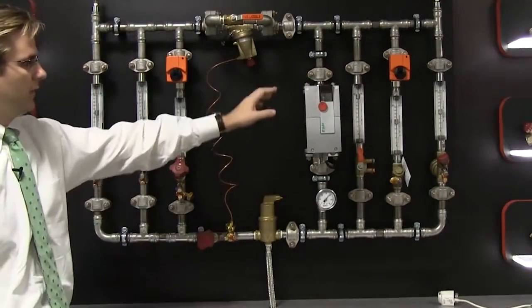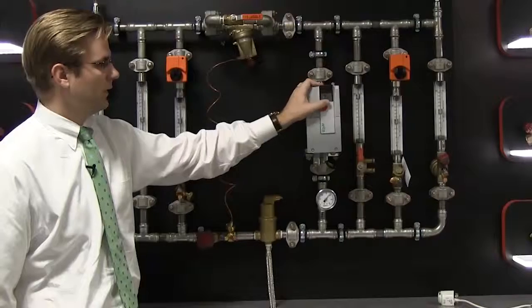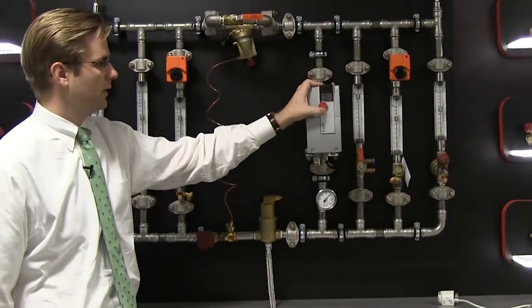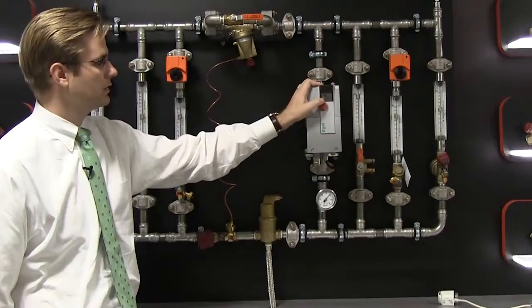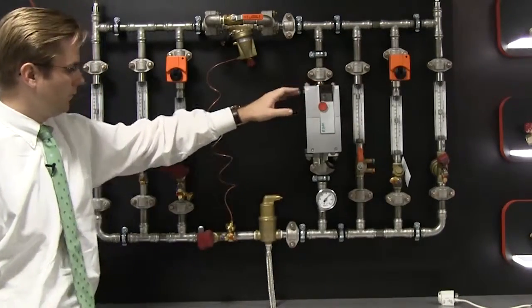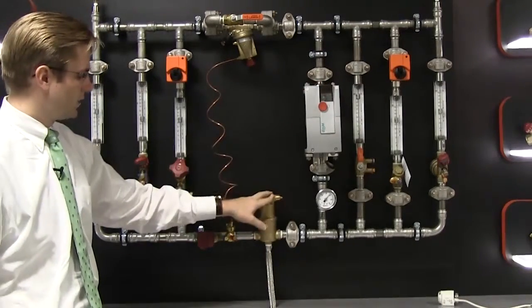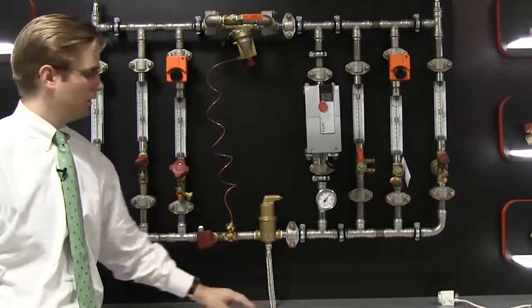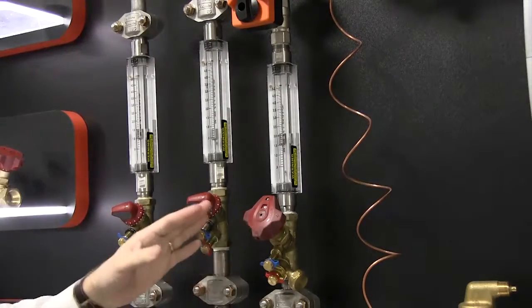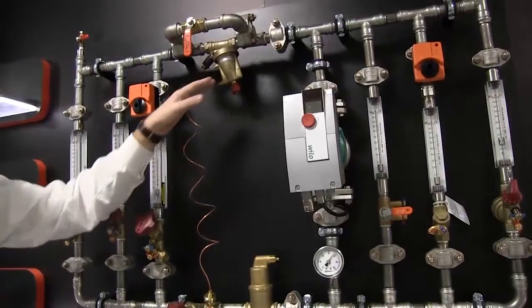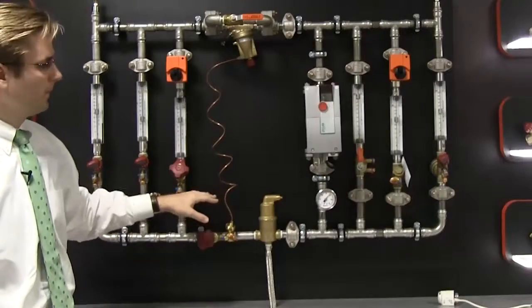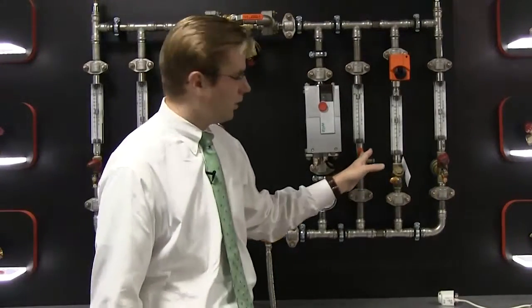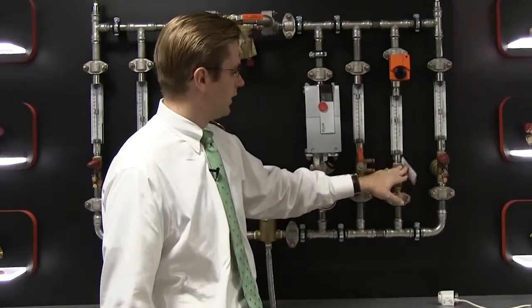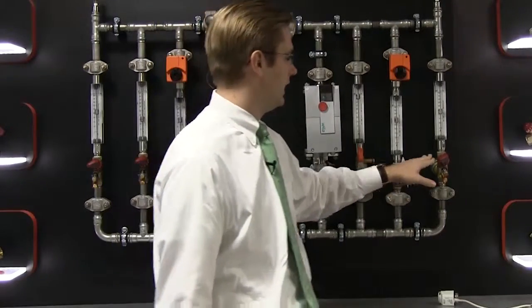On the flow loop, we have a variable speed pump that I can adjust the speed from a high range setting to a mid-range setting. We have an air separator with an expansion tank. We have 3 manual balancing valves and a differential pressure control valve. We have a ball balancing valve, an automatic balancing valve, and a pressure-independent balancing and control valve.